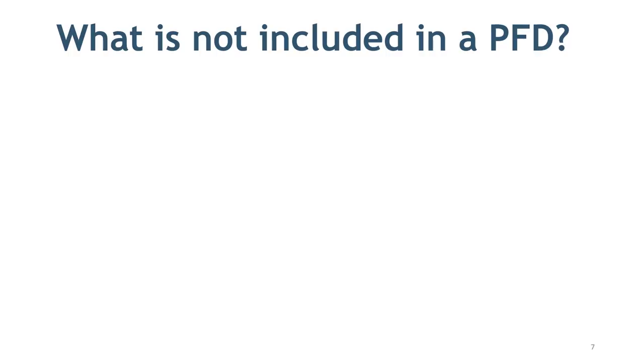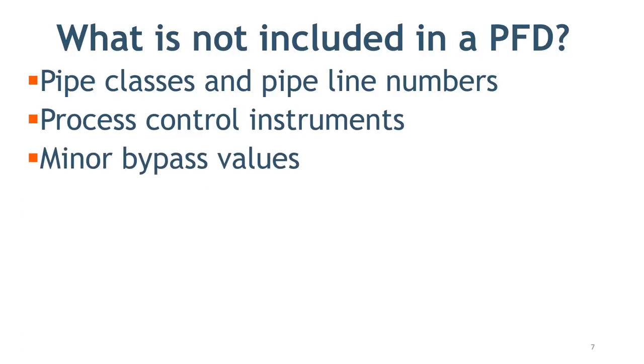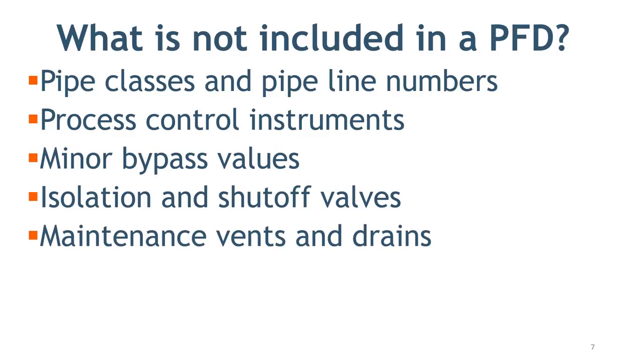What is not included in PFD? Pipe class and pipeline numbers, process control instruments, minor bypass valves, isolation and shutoff valves, maintenance vents and drains, relief valves and safety valves, and code class information.